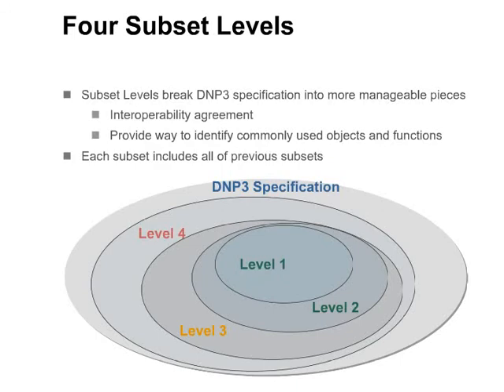The DNP-3 specification is very comprehensive. It would be impractical to try to implement every possibility described in the specification. Consequently, the DNP user group has adopted four subset levels. The subset levels break the specification into more manageable pieces. Each subset level represents an interoperability agreement between devices of the specified subset. Each subset defines a specific set of functionality that must be supported, and each subset includes all of the previous subsets.